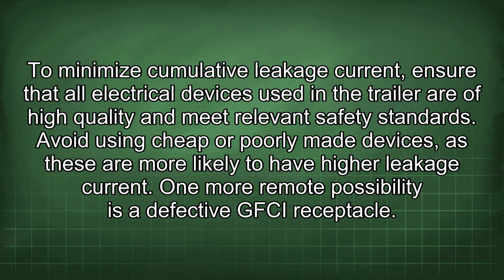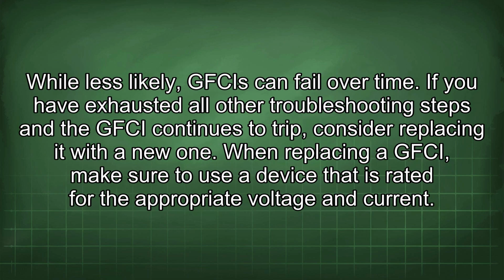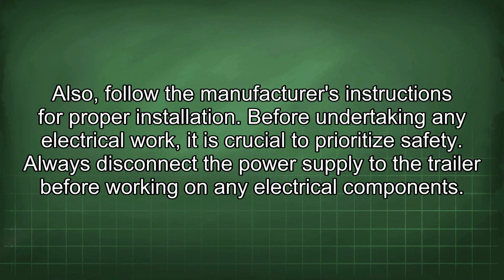One more remote possibility is a defective GFCI receptacle. While less likely, GFCIs can fail over time. If you have exhausted all other troubleshooting steps and the GFCI continues to trip, consider replacing it with a new one. When replacing a GFCI, make sure to use a device that is rated for the appropriate voltage and current. Also, follow the manufacturer's instructions for proper installation.